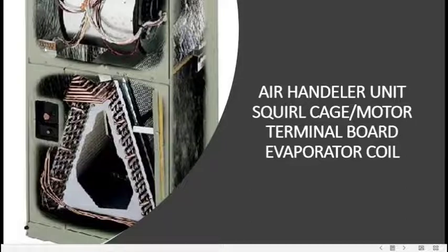Also over here. When in the heat mode, your heat strips will come on, or if this is a heat pump, your heat pump will come on, and if it's a W2, your heat strips will come on if it's too cold in the house and it calls for more heat than the heat pump can actually handle. If the heat pump outside freezes up, it'll shut off and energize W2, which brings on your heat strip. And the reversing valve will go back into air conditioning mode and defrost your condensing unit outside.